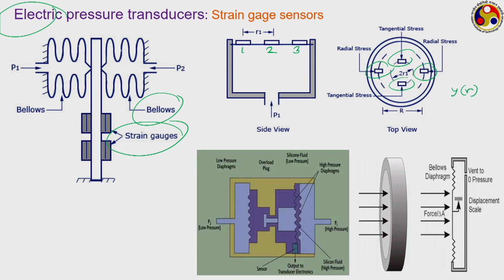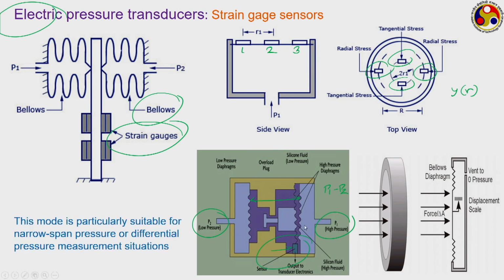This is another example. Again we are talking about a diaphragm, generally for a differential pressure measurement. On one side we have a high pressure P1 on one side of the diaphragm. There is a second diaphragm, a low pressure diaphragm, which has low pressure P2 on the other side, and the sensor is mounted at this particular location. This sensor is going to measure the deflection of both the diaphragms, particularly the high pressure diaphragm in this case, and then relate the distance between these two to the pressure difference, that is P1 minus P2. This P1 minus P2 can be directly related to the distance between these two diaphragms, which will be done by this sensor output. This type of strain gauge pressure sensor is particularly suitable for narrow span pressure or differential pressure measurement situations, just like shown in this particular example.